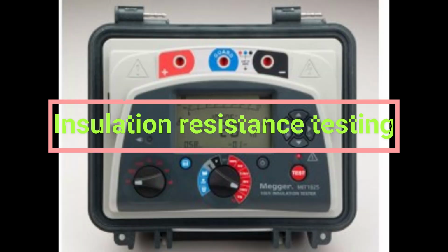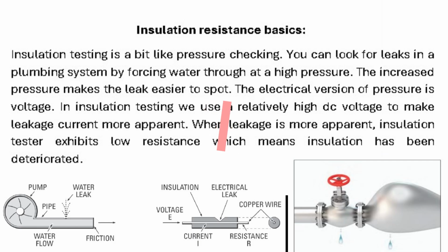Today we will discuss insulation resistance testing. Insulation resistance basics. Insulation testing is a bit like pressure checking. You can look for leaks in a plumbing system by forcing water through at a high pressure. The increased pressure makes the leak easier to spot. The electrical version of pressure is voltage. In insulation testing, we use a relatively high DC voltage to make leakage current more apparent. When leakage is more apparent, the insulation tester exhibits low resistance, which means the insulation has deteriorated.